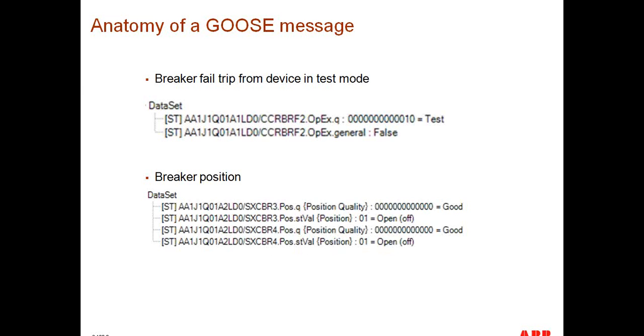Okay, let's go ahead. I have a few questions here. How can we reach a time of 3 milliseconds? Well, this is the amount of time it takes the device to compile the Goose message and then send it over the network. There's obviously a network transmission time, but for all practical purposes, if the information is being exchanged inside a substation, the physical distance is pretty much negligible given the transmission speed of such messages, so you're going to be at 3 milliseconds or less for sure. Speed is really a measure of bandwidth and the distance the message has to travel, and IEC 61850 defines a network speed of 100 Mbps or above, so that is not a problem to achieve.